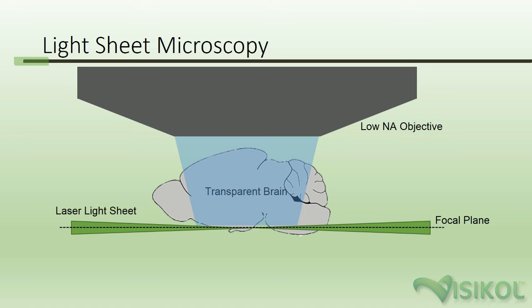The way a light sheet microscope works is by switching from an inverted or upright diffuse light source to a laser light source that is mounted orthogonally to the objective. Using cylindrical shaping lenses, the laser light sheet is transformed into an ultra-thin sheet of light that is, for example, 10 millimeters wide by 5 microns thick.